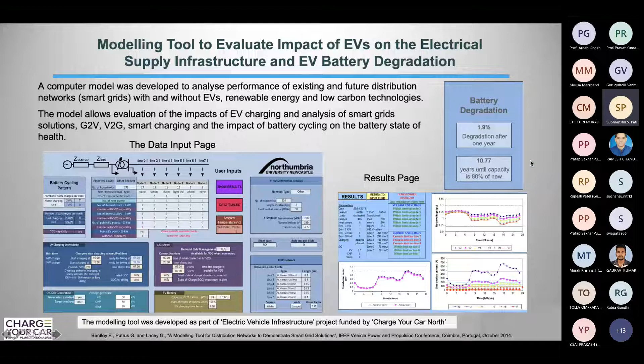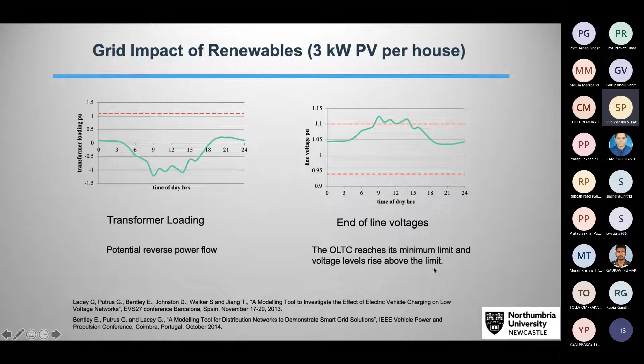We used that tool to study the impact of renewable energy and electric vehicles, and you can see here the grid impact of renewables. We assumed 3 kilowatt PV per house. You can say 6 kilowatt in one house, 0 PV in another house, and so on. But it was just an assumption, really, just to see what happens to the transformer loading and end line voltage. And you can see here they exceed limit. There is potential reverse power flow, and there is potential over voltage as the on-load tap changer reaches its limit.